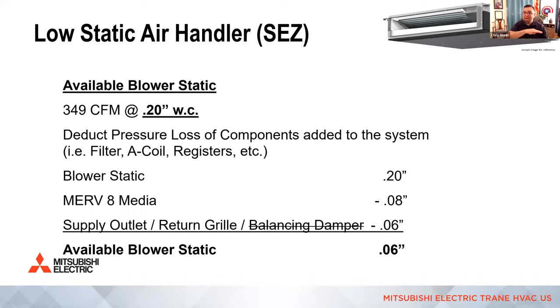Now, you'll notice I slashed balancing damper. When you design a low static air handler, we're most likely not going to have enough static pressure to handle even just an additional balancing damper if we're adding a MERV 8 media filter. So if we don't add a good filter, then we can handle that pressure drop of a balancing damper. So typically the rule becomes with low static air handlers, we don't install balancing dampers. But that's because there's so little ductwork going to the system that you probably don't even need it, because it goes to one or two rooms anyway, okay? That's the only reason. It's really around this.